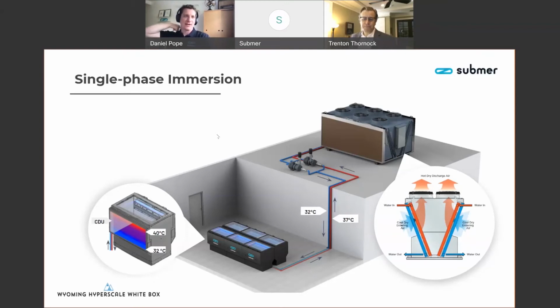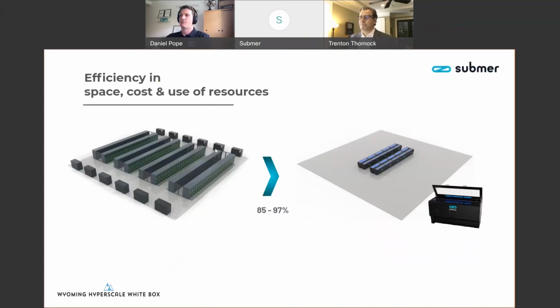So talking about that, on our next slide we have the typical image we love to show, which shows the density comparison of a 2 megawatt data hall based on 10 kilowatt racks, which is quite normal to see today. A pretty common hot aisle, cold aisle layout with CRAC units, which may or may not have mechanical rooms, but that's still the traditional build, versus high density 100 kilowatt immersion tanks and the space they require.